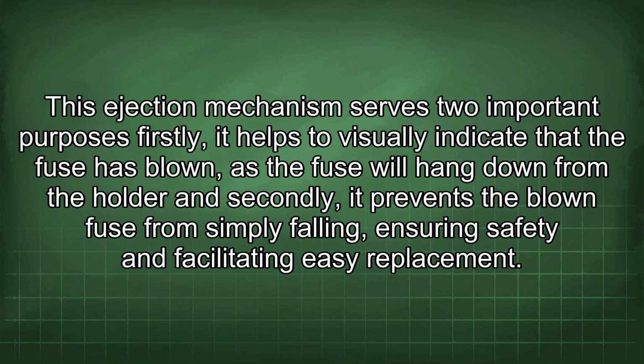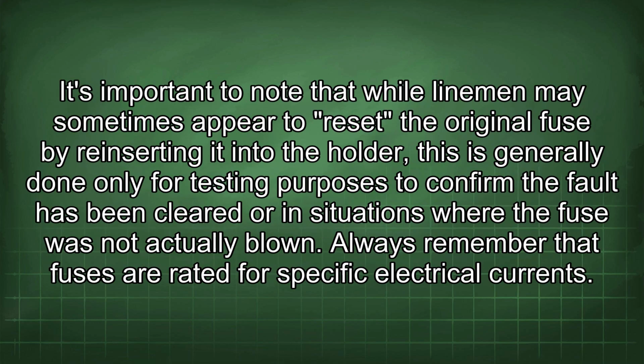This ejection mechanism serves two important purposes. Firstly, it helps to visually indicate that the fuse has blown, as the fuse will hang down from the holder, and secondly, it prevents the blown fuse from simply falling, ensuring safety and facilitating easy replacement. It's important to note that while linemen may sometimes appear to reset the original fuse by reinserting it into the holder, this is generally done only for testing purposes to confirm the fault has been cleared or in situations where the fuse was not actually blown.